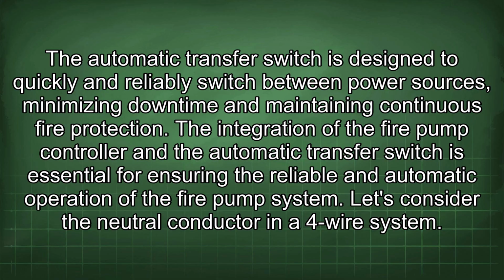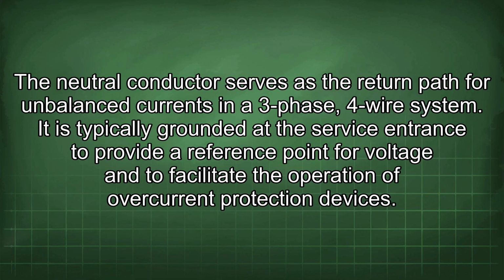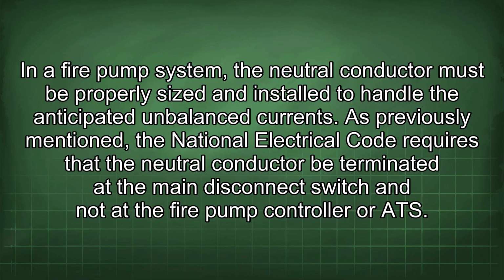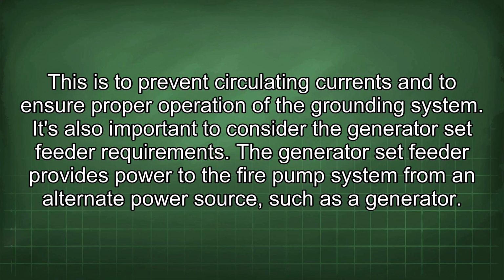Let's consider the neutral conductor in a four-wire system. The neutral conductor serves as the return path for unbalanced currents in a three-phase, four-wire system. It is typically grounded at the service entrance to provide a reference point for voltage and to facilitate the operation of overcurrent protection devices. In a fire pump system, the neutral conductor must be properly sized and installed to handle the anticipated unbalanced currents. As previously mentioned, the National Electrical Code requires that the neutral conductor be terminated at the main disconnect switch and not at the fire pump controller or ATS. This is to prevent circulating currents and to ensure proper operation of the grounding system.